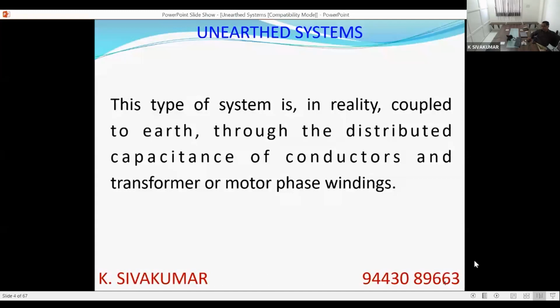Here also in this network there will be conductors and there will be dielectric. If you take an overhead distribution line, the overhead line will be one plate of a capacitor. Natural ground will be the other plate of the capacitor. The dielectric in between, air, will be acting as a dielectric, and a capacitance will be formed. So there will be an imaginary capacitive coupling, even though we cannot say wired coupling. There will be a capacitive coupling throughout the system. It will persist. Even though we say physically unearthed, it will be a capacitively earthed system.